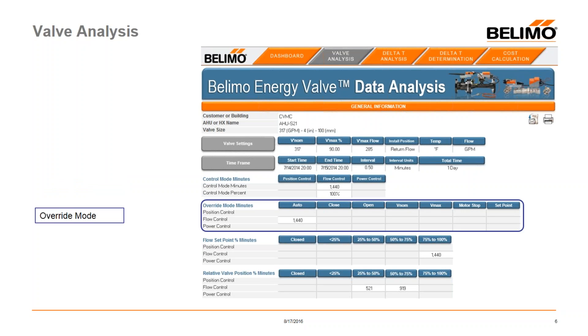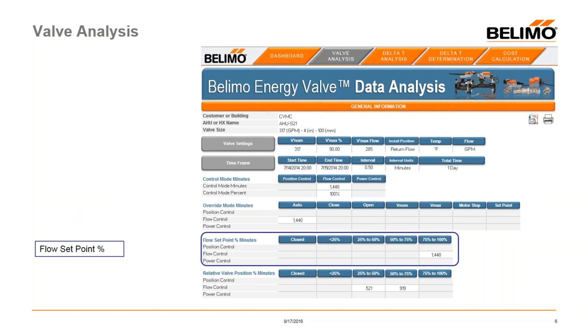The override mode section, again broken out by the three types of control, tells you how many minutes someone may have logged into the valve and overrode the control. You can go inside the valve through WebView, take control, open or close the valve, stop it, or change set points. If you override the valve, that will change your data set, and that's something you need to be aware of.